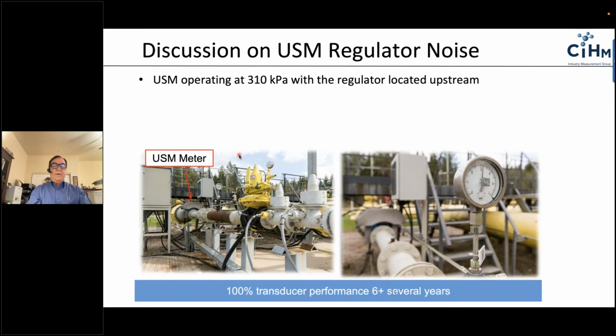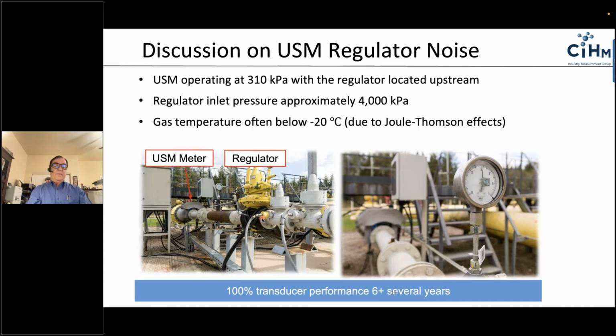So here we have a meter installation package. This is the ultrasonic meter running at about 310 kPa. About 4,000 kPa is immediately upstream of this regulator. You can see the regulator directly in line with the meter with just 2 flow conditioners in the middle to stabilize the profile. The gas temperature is typically -20 C and colder due to Joule-Thomson.